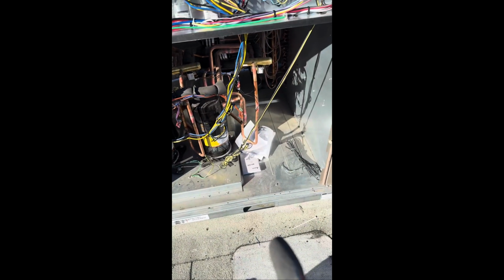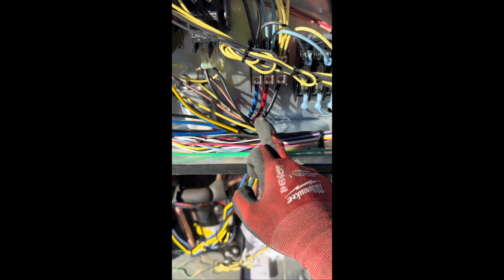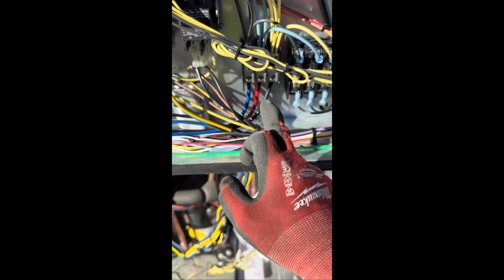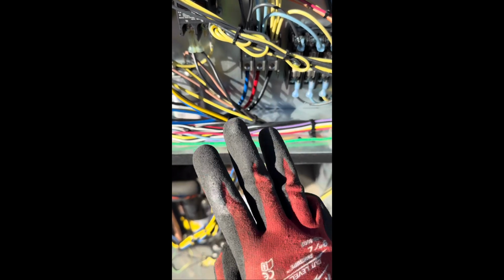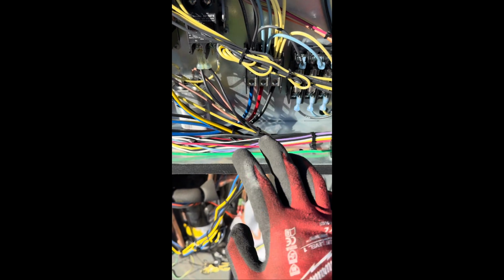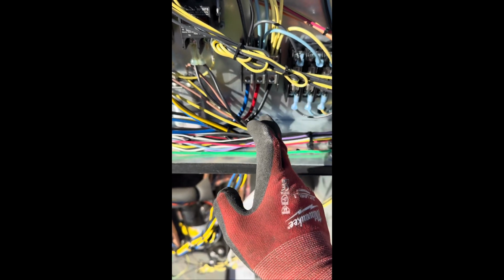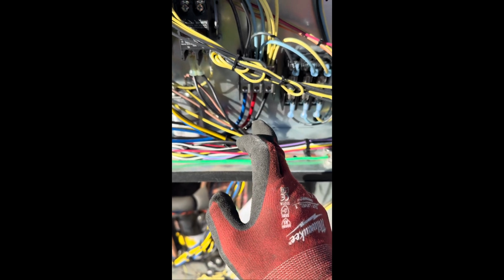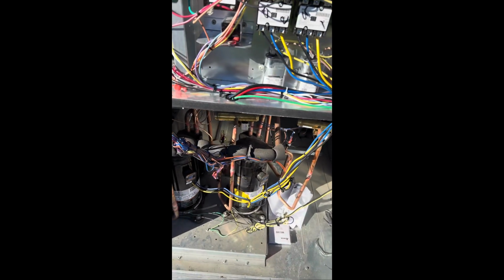Now, another thing with these York units, according to the manufacturer instructions, we have to check the high voltage here. So we have A, B, C, or L1, L2, L3, because we're working on a 3-phase system. We check for the high leg, which would be whatever the greater voltage is of the 3 legs, and that'll be connected to L2 or the B terminal block here. So once we verify that, we can hook up our gauges, make sure that the compressor is running correctly, and that should take care of that.